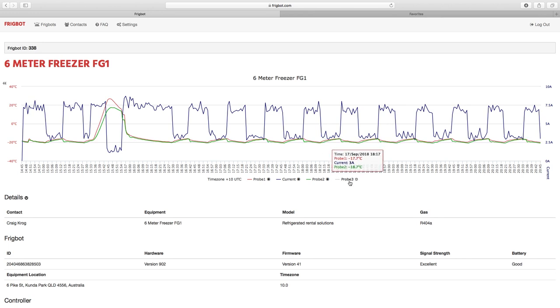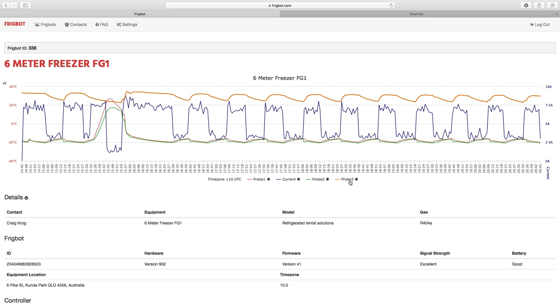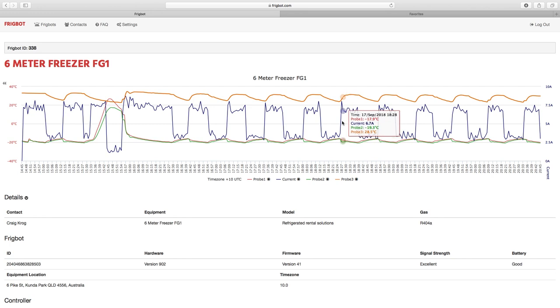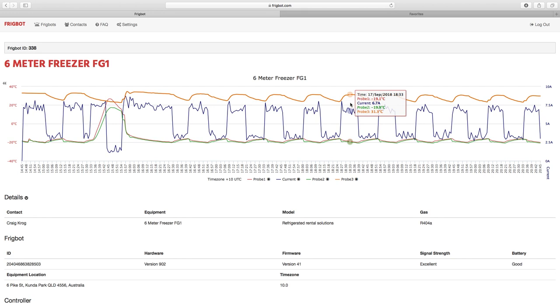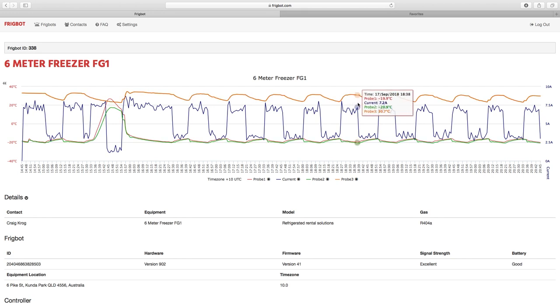Probe number 3 has been hooked up to the liquid line which is on the condensing unit, and in this case we're using the same controller to cycle the condenser fan. And there we can see the liquid line temperature increase, the fan comes on, the condenser fan reaches its desired temperature set point and that cycles off.